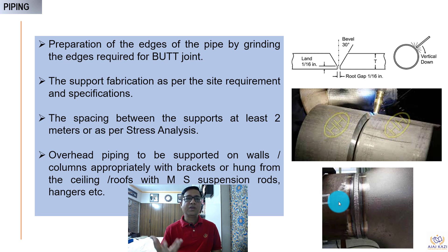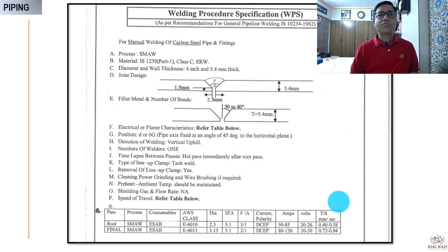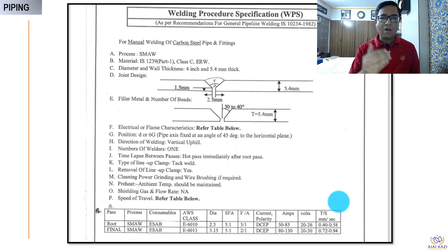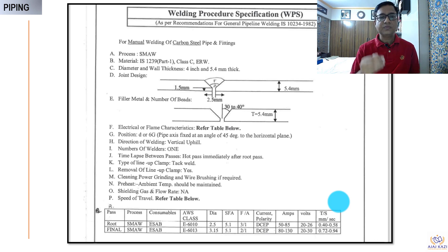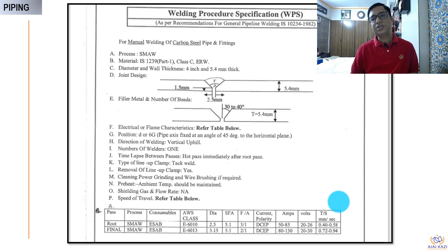Support fabrication will have specifications governing it, or we can do a stress analysis to know the exact stress and determine the right support size. Generally pipes are hung from the ceiling, columns, or floors depending on the situation. This is the welding procedure — WPS per IS 10234 — which specifies how the welding process is to be done and whether the welders are qualified. Key parameters include vertical uphill direction of welding, time between passes, removal of line-up, and cleaning by power grinding or wire brush.